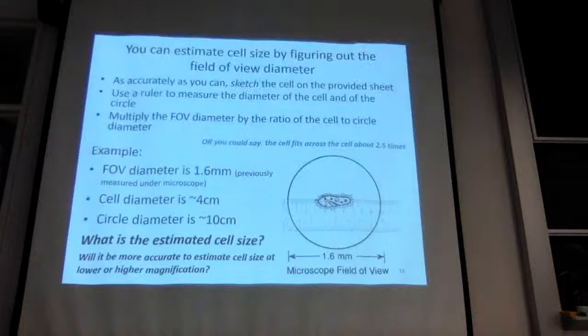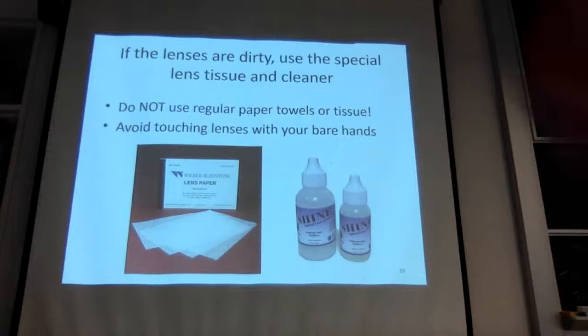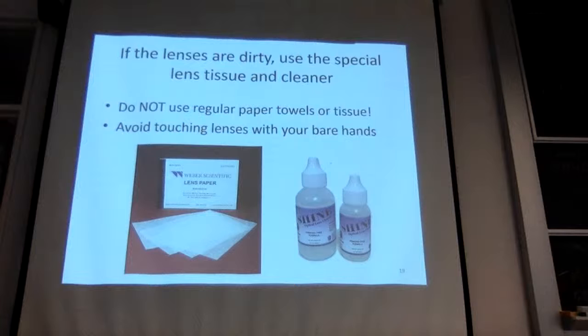Some last few things about microscopes. It often gets dirty — dust gets on there or people touch it. Please try not to touch your fingers on the actual lenses. We constantly produce oil and sweat, so we don't want to get that on the lenses. If it is dirty, at the end of each table we have special lens paper. Don't use paper towels because that will scratch. We have special lens paper and blue lens cleaner — only use these things to clean the lenses, whether it's the ocular lens, the objective lenses, or anything. You can even clean the slides.